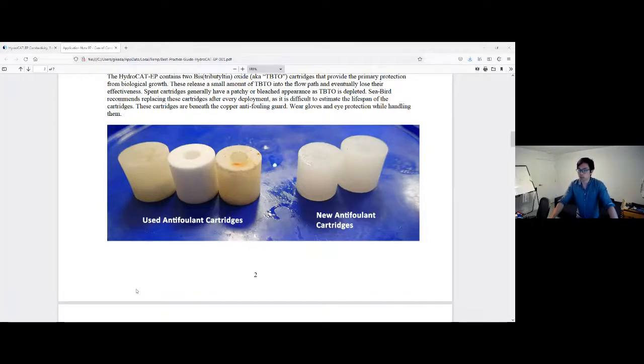What I would also recommend doing is checking out your minimum conductivity frequency more often. As we mentioned before, or I'm sorry, your zero conductivity frequency. Take a look at that 0 value, send a TS command, and see what the raw output from your conductivity sensor is telling you. If it's quite a bit different from that 0 conductivity frequency from calibration, say 1 or 2 hertz off, it's possible that you're getting biofouling in your instruments, and these cartridges need to be replaced.